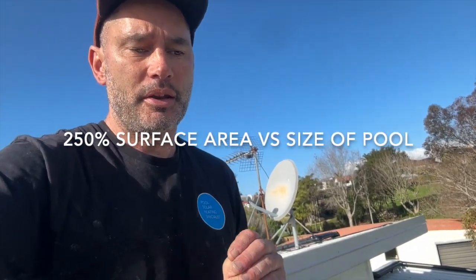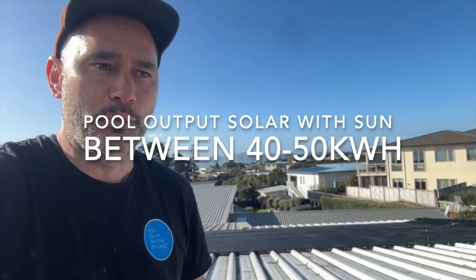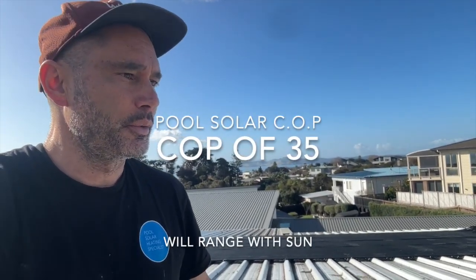The difference between heating the pool with pool solar versus using an appliance or heat pump is the output of the pool solar system. This current system at 250% is sitting somewhere around, with sun, probably outputting between 40 and 50 kilowatts equivalent. The COP on this is probably sitting in and around or above 35.